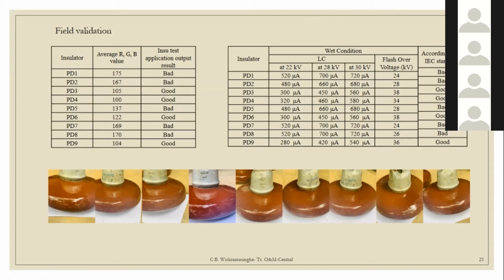Then, in order to prove field validation, I chose 9 insulators from the field. I calculated the RGB value from my application, then took them to the HU laboratory and measured the leakage current at wet condition. The laboratory results and my application results were synchronized 100%.